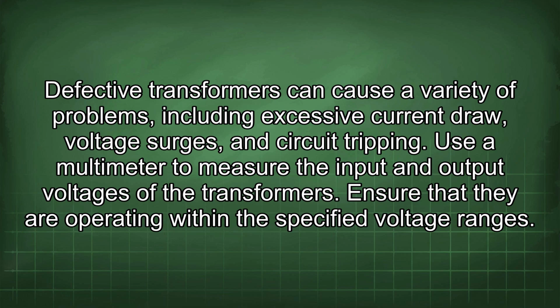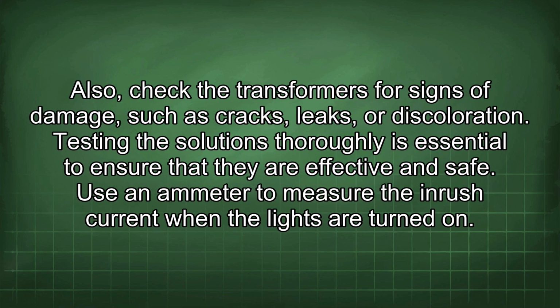Defective transformers can cause a variety of problems, including excessive current draw, voltage surges, and circuit tripping. Use a multimeter to measure the input and output voltages of the transformers. Ensure that they are operating within the specified voltage ranges. Also, check the transformers for signs of damage, such as cracks, leaks, or discoloration.